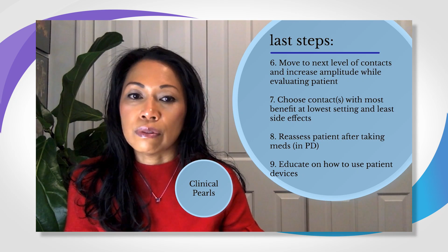Some clinical pearls as you're programming: the stimulation benefit on rigidity can last from a few seconds to a couple of minutes, so it's best to let the stimulation wash out between contacts—turn off the stimulation and wait a minute before turning it back on for the next contact.